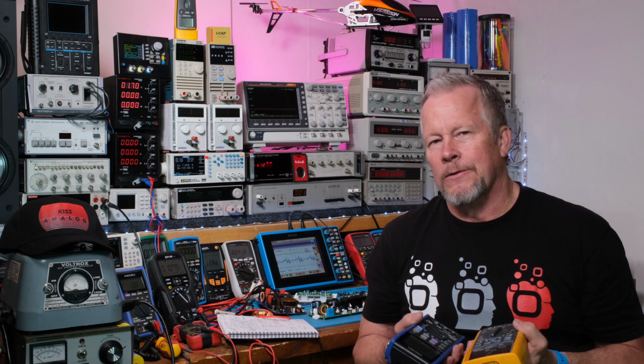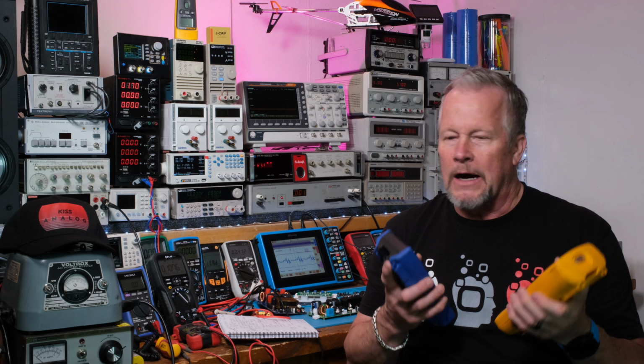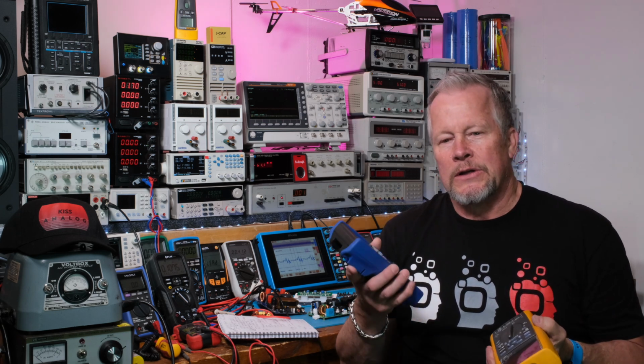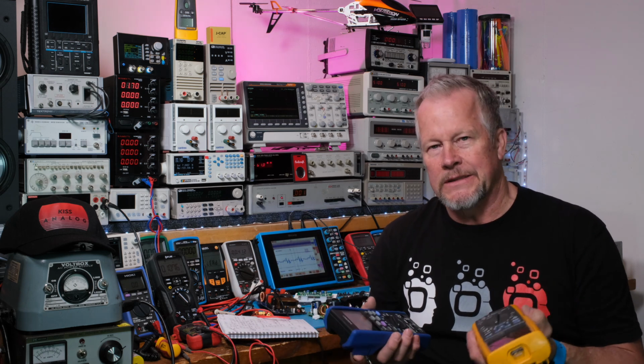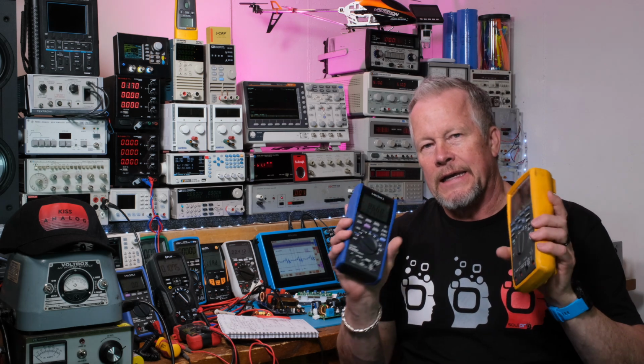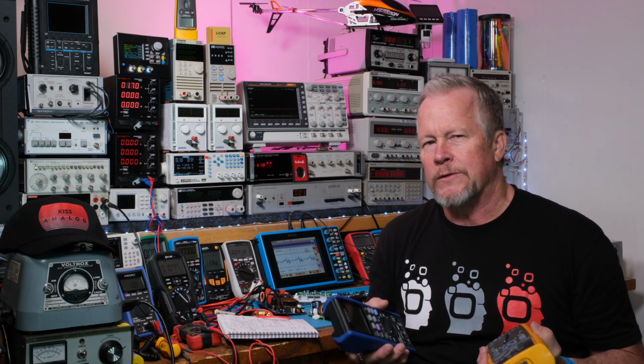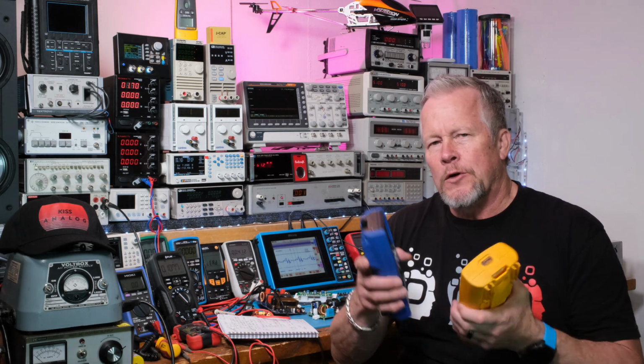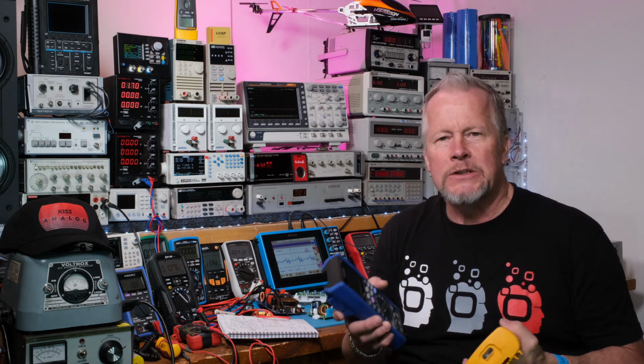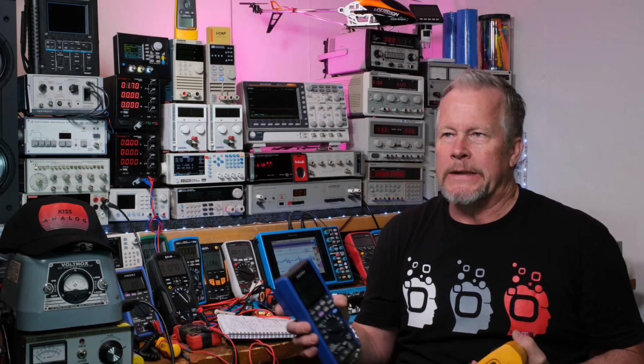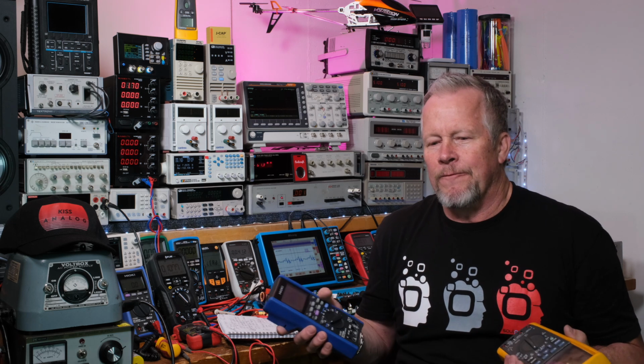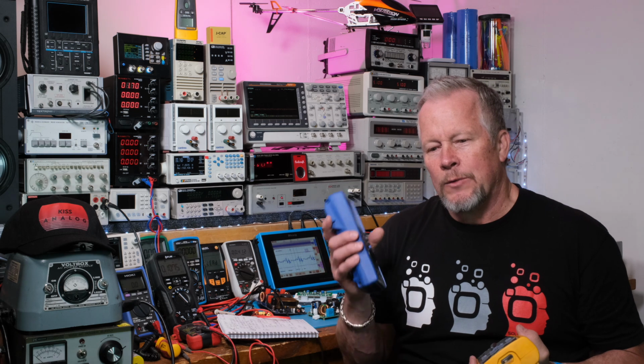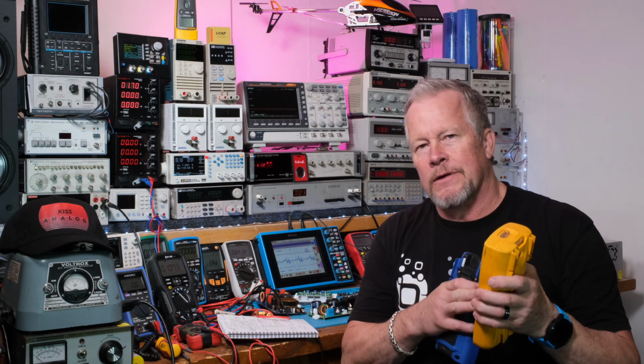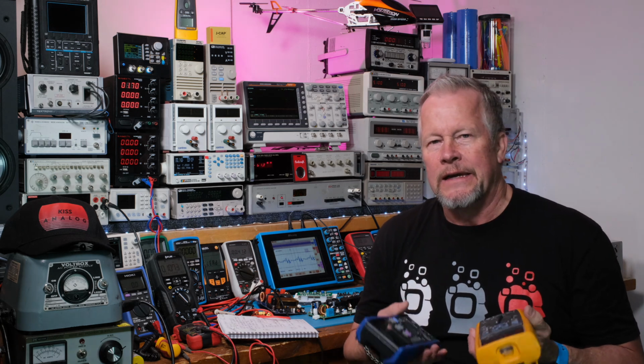Another thing is the decibel. You can get gain. If you're doing audio work, for instance op-amp work, you can look at the input and the output and take gain measurements with the decibels. That's another cool thing you get with high-end meters. A lot of times now, even with lower-end meters, you can get the VFD filter, right? The variable frequency drive. When you're taking AC measurements, it can filter out the noise from that variable frequency drive, and you can use that for other things as well. Because it has a 1 kilohertz bandwidth, let's say on a 6,000 count meter, that filter might be at 400 hertz. Well, with these higher end meters, you have a way of tuning that. You can change that bandwidth. That's a really cool feature as well.